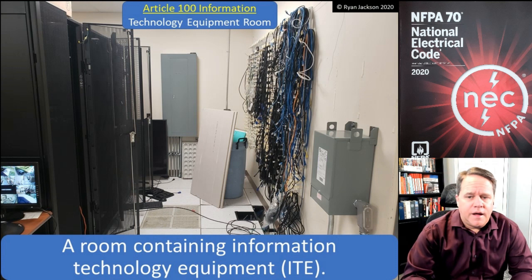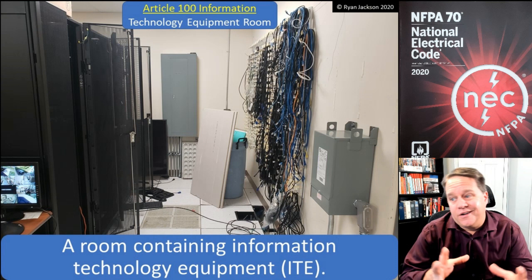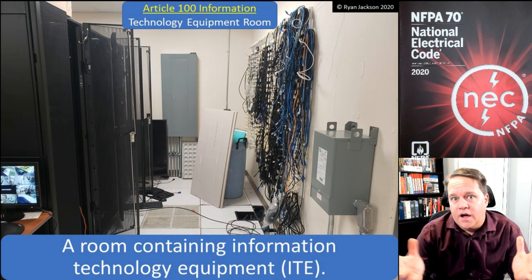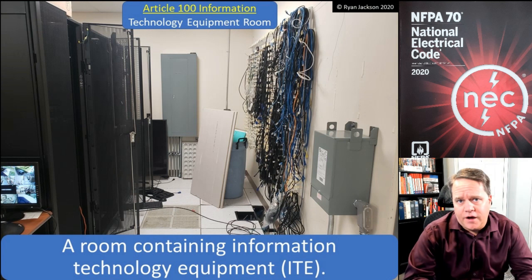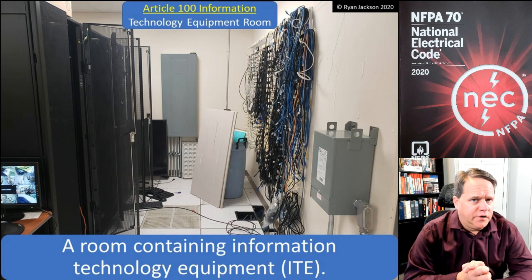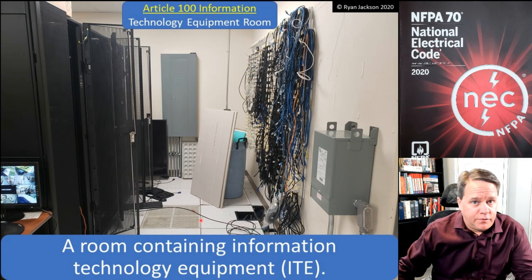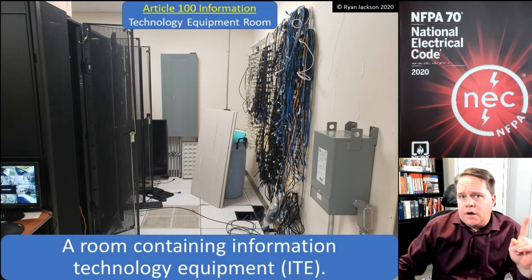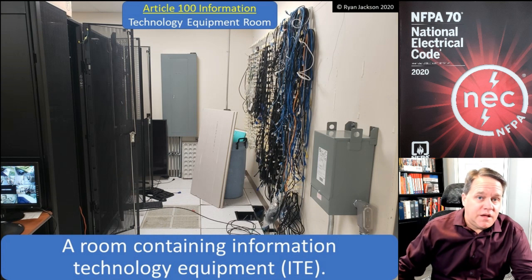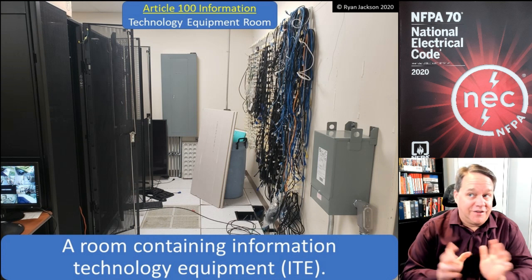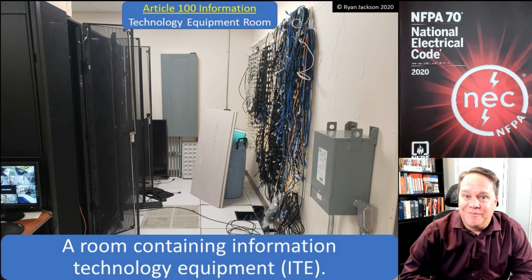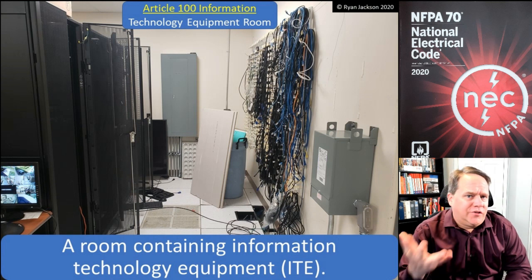We're also going to be running cables through that raised floor. Forty years ago when we first started doing computer networking as we'd recognize it today, we didn't have very good cabling systems. Then requirements for plenum ratings were added for cables used inside areas used for air handling. Under 300.22, cables in an area used for environmental air have to be plenum rated, but back then you couldn't get a good plenum rated cable — maybe Cat 3 or whatever it was — that could handle the needs of an IT room.